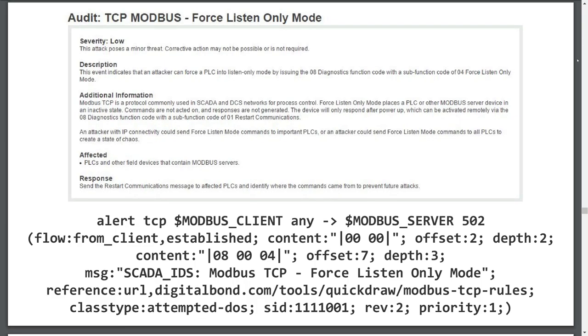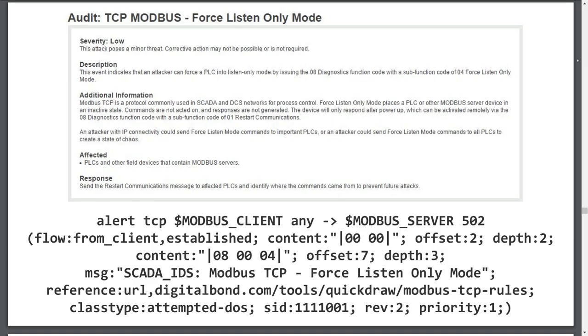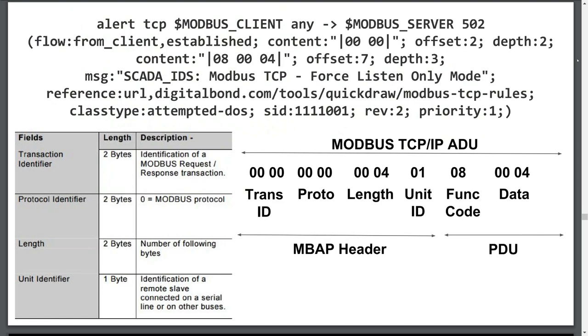So what is the signature for? A semantic report states that an attacker can force a PLC into listen-only mode by issuing a 08 diagnostics function code with a subfunction code of 04, representing force listen-only mode. Essentially, this places the PLC in an inactive state and creates a denial-of-service event. Remember, the attacker doesn't necessarily need to compromise the system, rather prevent functioning or simply degrade its ability to perform. The signature detects the bytes listed in the bottom-right Modbus TCP IP ADU.